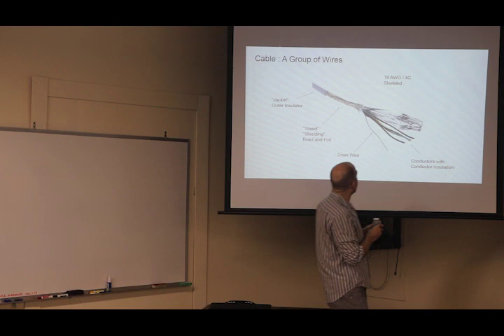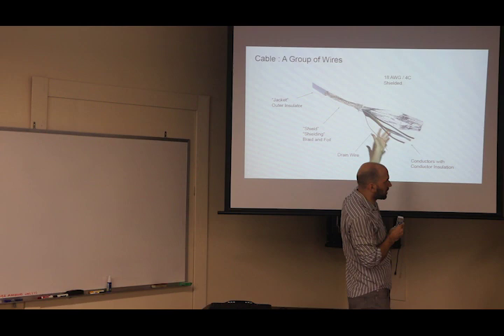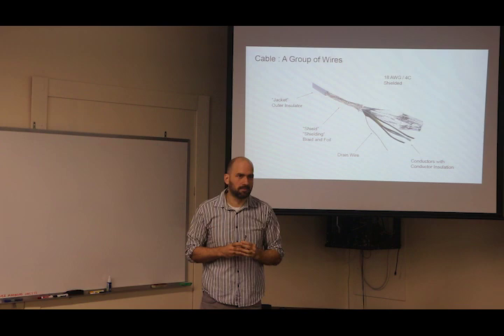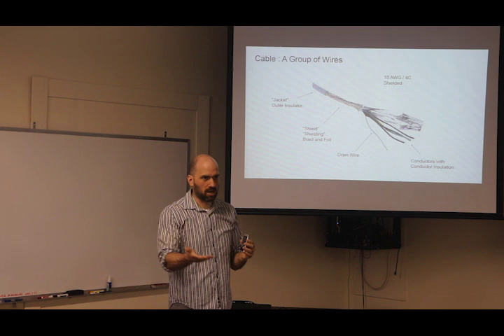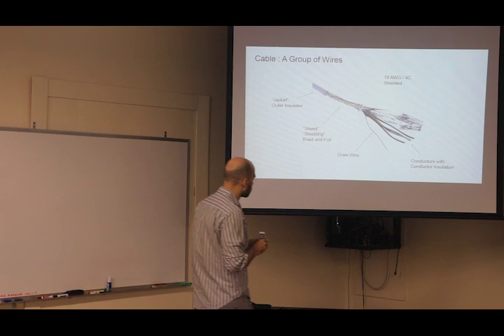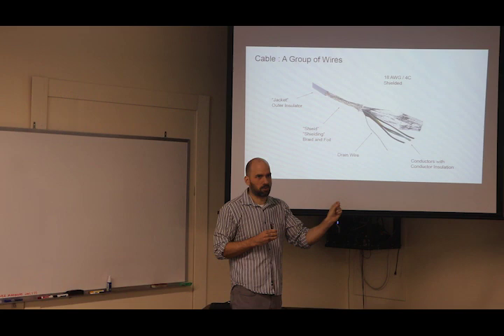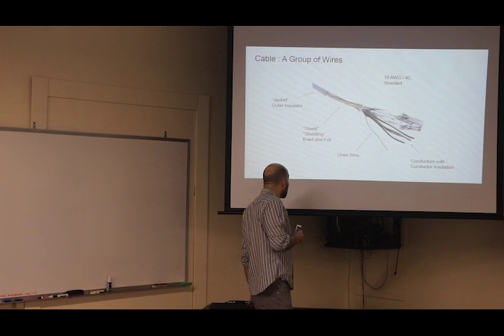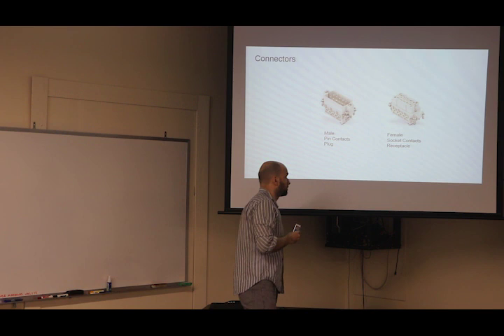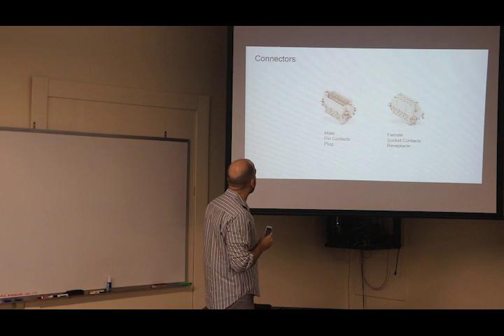Shielding is optional, and that's mostly for interference because you have radio waves and you have cross-talk between different cables potentially. Shielding is a pain unless it's necessary, and then you just have to deal with it. When you're picking out cables, that's really the important thing to pay attention to: shielding, what the gauge is, and then how many conductors are in there. That's the gauge of each individual wire, the 18 gauge? It is, yes. You can have a cable with multiple gauges in it. Say, for instance, you want to run a big motor with it and also want to tell the motor when to turn on and off. You have a couple small wires for the signal portion and then big wires.